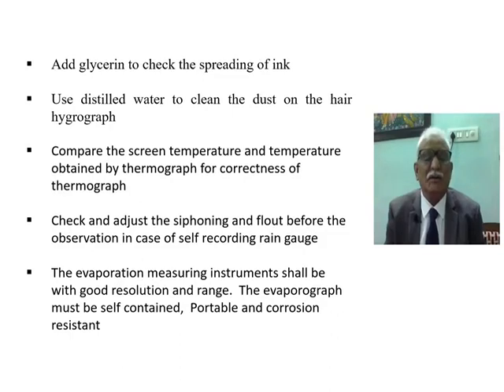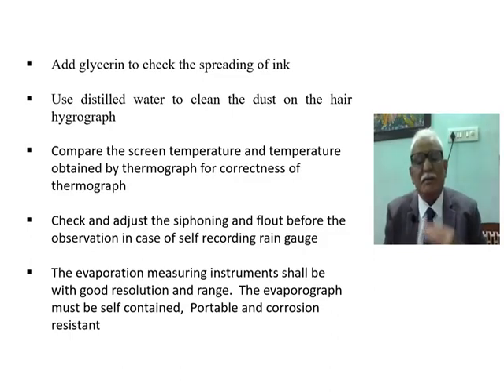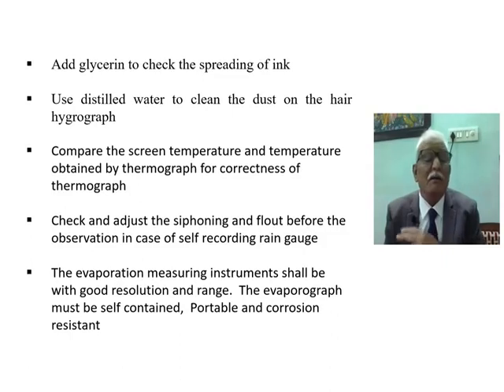Clean the dust with as much clean or distilled water as possible so that the hair hygrograph gives correct continuous recording of humidity. Compare the screen temperature and the temperature obtained by the thermograph for correctness. The dry-bulb thermometer, wet-bulb thermometer, and thermograph are all present in the same observatory, so careful comparison among thermometers is essential.